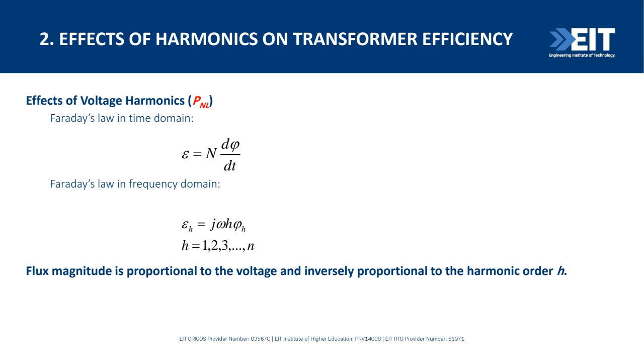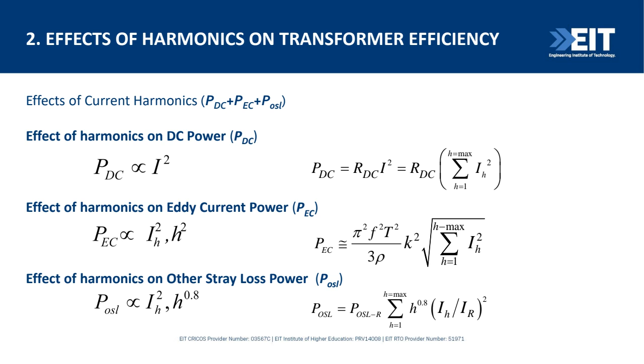Again, nonlinear loads can cause additional losses in the associated distribution transformers. We do have effects of harmonics on DC losses, which are proportional to I squared, and eddy current losses in the conductors, which are proportional to I_h squared and h squared. h is actually the harmonic number. When we're saying the second harmonic, h is 2. For the third harmonic, h is 3. And we do have effects of other stray losses, which are proportional to I_h squared and proportional to h to the power 0.8. I'm not going through the details of these formulas. These are coming from the standards that I mentioned earlier. So what we know is that all those current losses are proportional to I squared, which is very important.